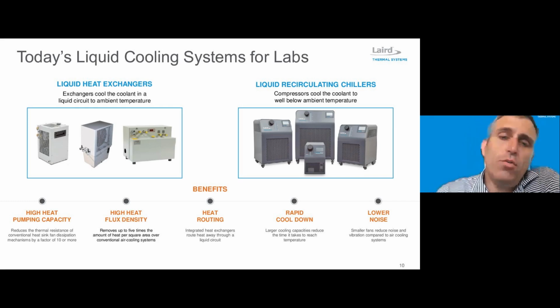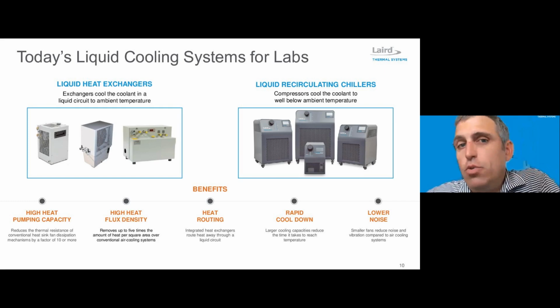And we can work with those irregularities of temperature and flow to provide the customer with a real precise coolant loop. We also offer products that can cool below ambient temperatures, and we do this 2 ways. We do this with thermoelectric technology, and we also do this with refrigeration systems. So these are vapor compression systems. The common thread amongst most of the products we make here is that they have a pump circulating fluid out to the customer's application.